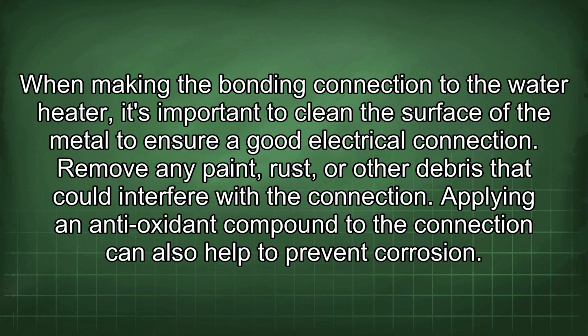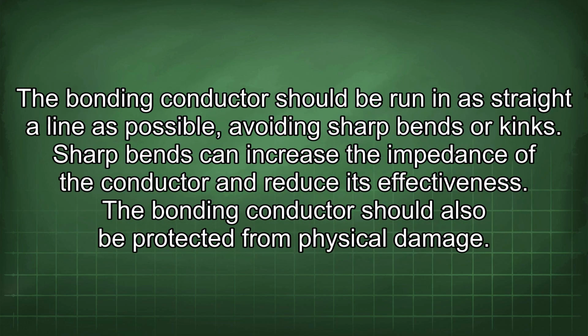When making the bonding connection to the water heater, it's important to clean the surface of the metal to ensure a good electrical connection. Remove any paint, rust, or other debris that could interfere with the connection. Applying an antioxidant compound to the connection can also help to prevent corrosion. The bonding conductor should be run in as straight a line as possible, avoiding sharp bends or kinks. Sharp bends can increase the impedance of the conductor and reduce its effectiveness.